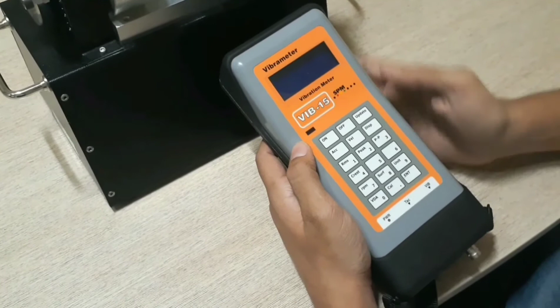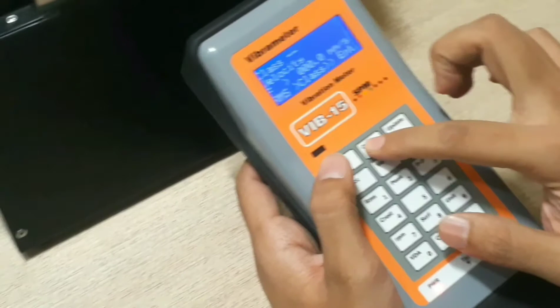These are the function keys available on our VIB-15 vibration meter. On button, as you can see, while pressing this you can switch on the instrument, and there is also an off button. We can see here an update button. We can measure vibration in terms of acceleration, velocity and displacement with respect to RMS, peak and peak to peak. We also have an option called crest factor.